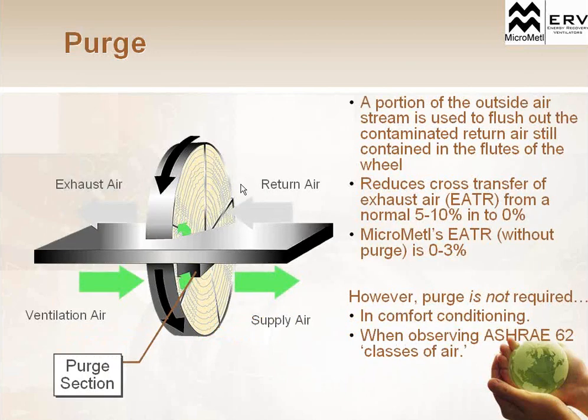Now, in instances where we do get leakage, there is a way that we can use a purge fan or purge angle to reduce that leakage. If we look at the exhaust air out of the building on the top of this energy recovery wheel and then the supply air into the building, as I said, we had a pull-through fan on the exhaust air of the system and a push-through fan on the bottom. Some of the air coming across is diverted up and along the inside of the wheel. So it's going through and up and then back out. This is pushed through the wheel and up to prevent any of that return air coming down. So that reduces any cross-contamination of return air into fresh supply air. That air coming up would push that air across the wheel and prevent it from coming down back into the supply.